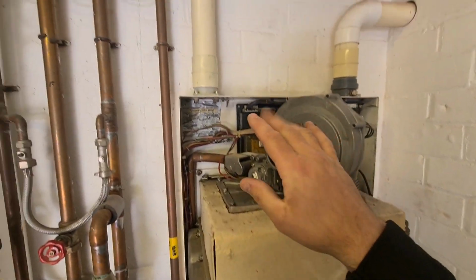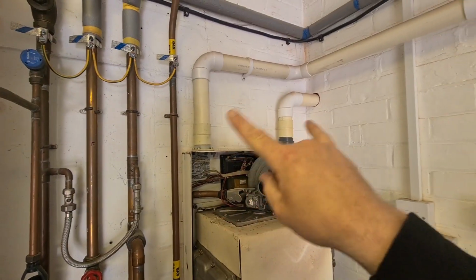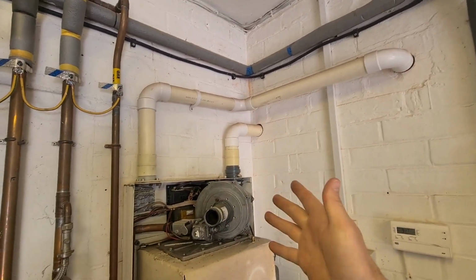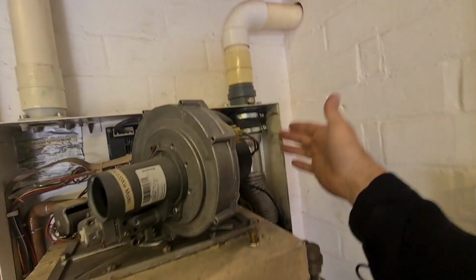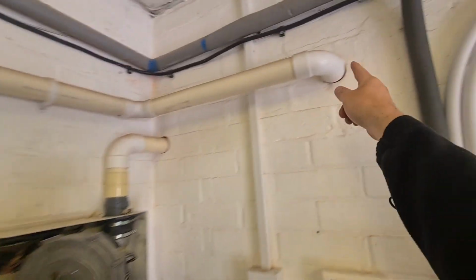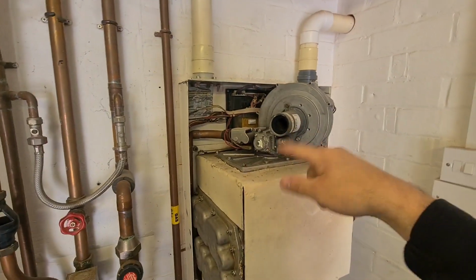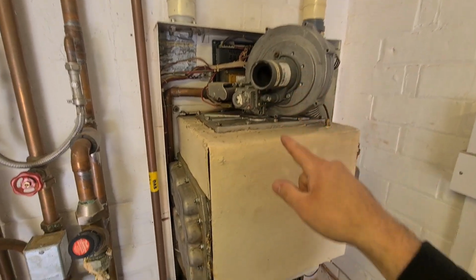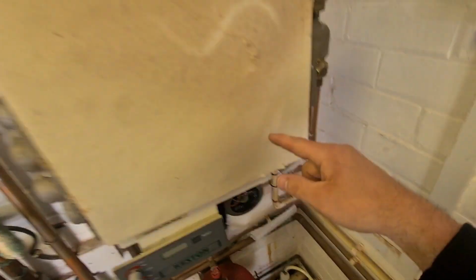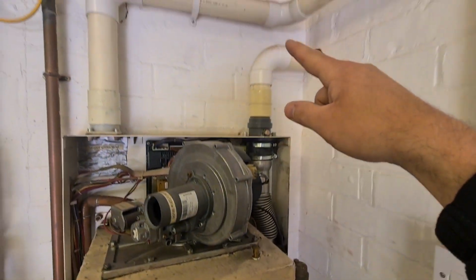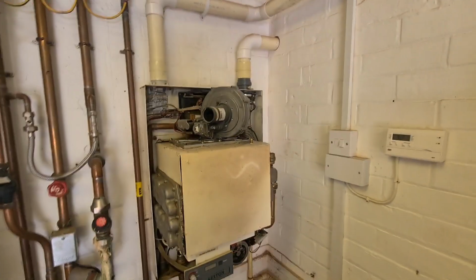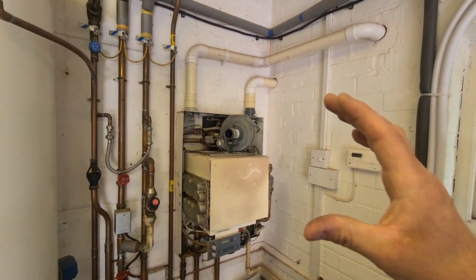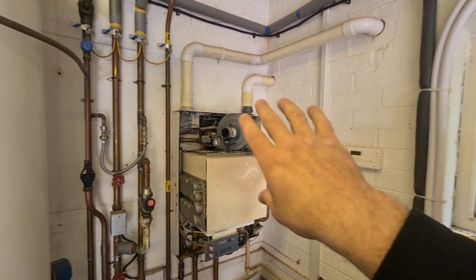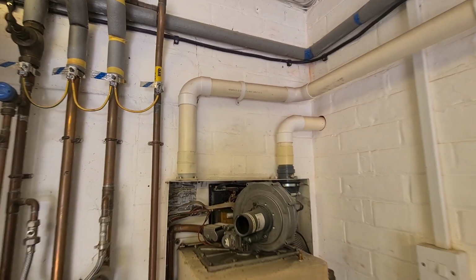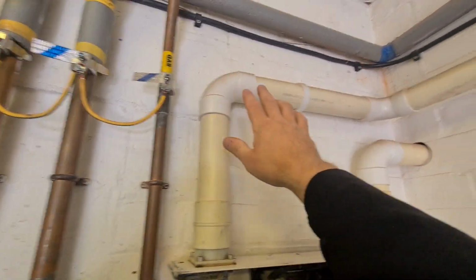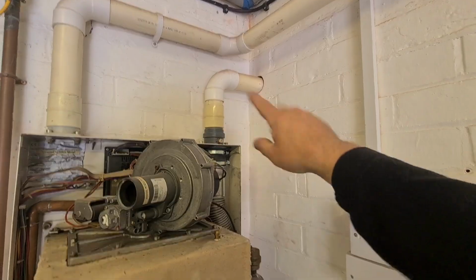Whip the burner out, check what's going on inside. This one, some of you guys might not have seen this, and some people are afraid of this, but again, it's a flued system, air intake, air outtake, pretty simple. It drags air into the burner, gets drawn into the fan through the combustion process, gets ignited, comes back up, and the exhaust fumes get blown out. So again, simple, but a lot of people see nowadays just the twin flues, which is a 4-inch flue that goes straight out. Again, nothing to worry about with these. We're just going to check the simple little things, making sure that everything is intact, glued, do our flue integrity check, and then we're happy with that.